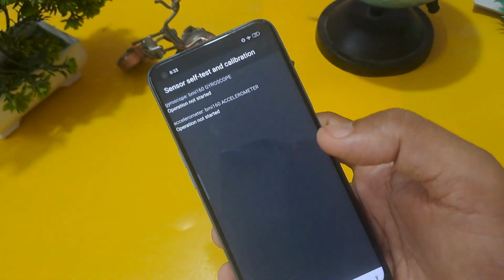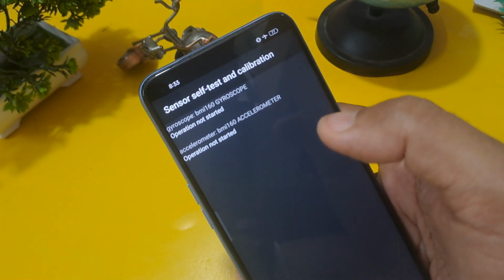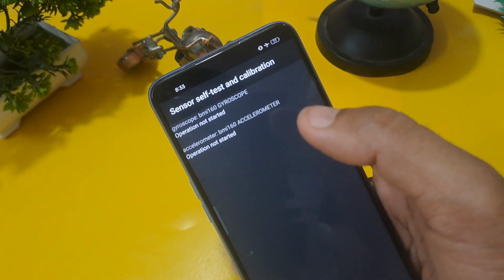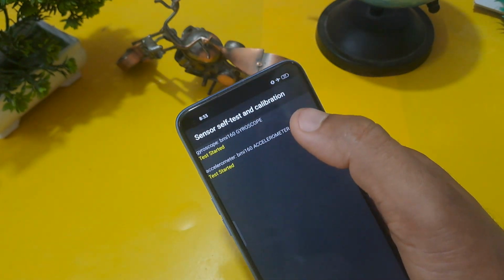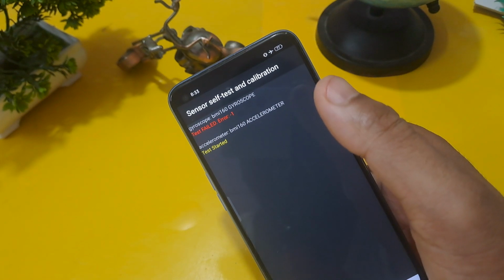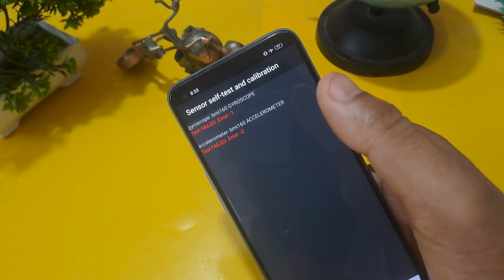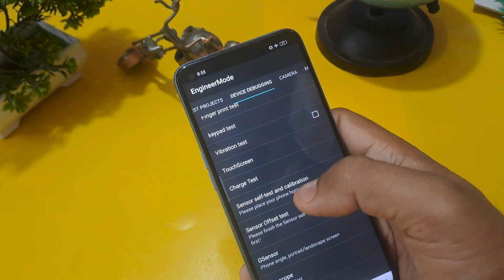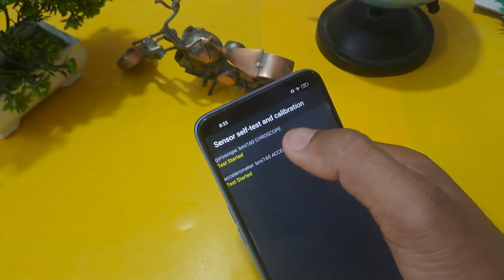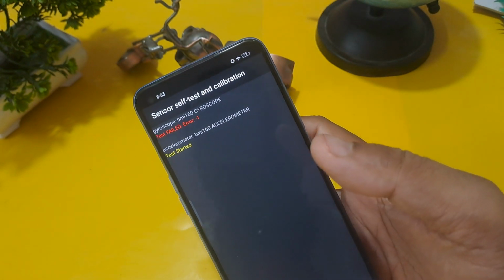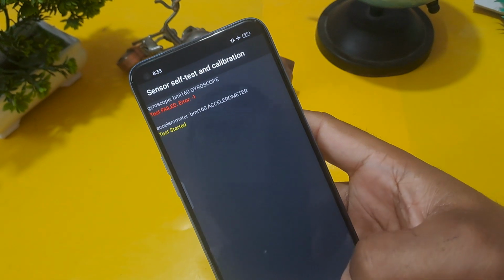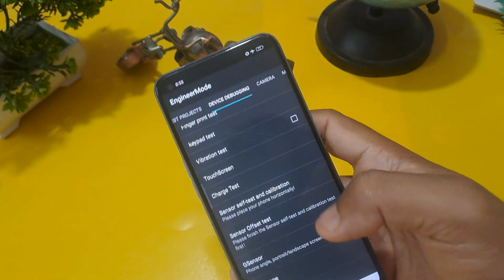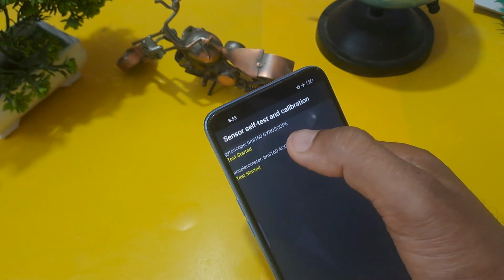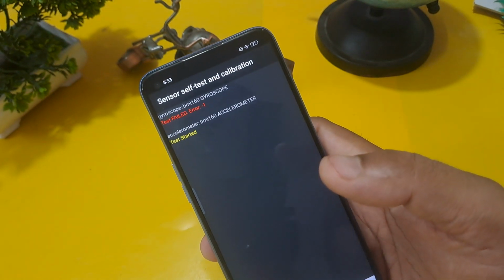Check sensor self-test and calibration, and finally you can see gyroscope and accelerometer operations not started. At least one must be started here, and at least one must show a test pass in each of them.